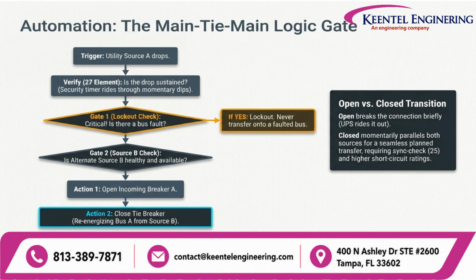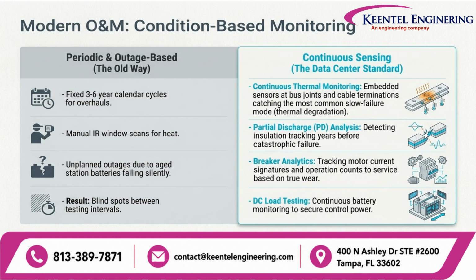Automation logic in a main-tie-main setup must be robust. It should verify source drops, check for bus faults, and confirm the availability of alternate sources before taking action. Differentiating between open and closed transitions is also critical for system stability. Modern operations and maintenance favor continuous, condition-based monitoring over periodic, outage-based testing.